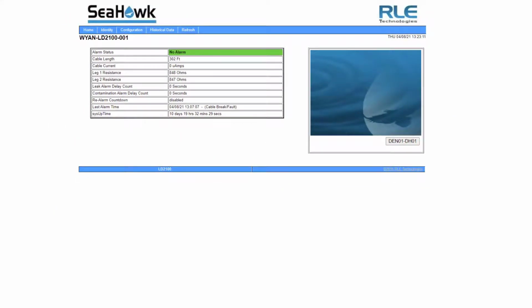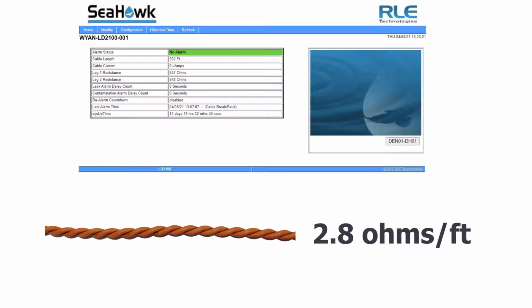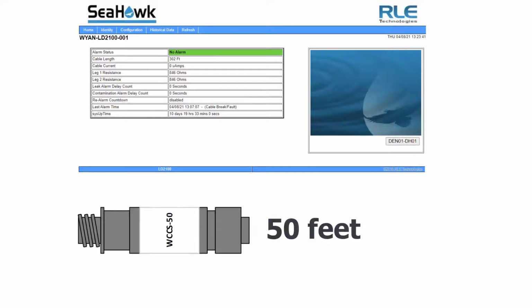So going into calibration, you always want to check for a few optional components being added onto that cable system. The sense cable itself has an approximate 2.8 ohms per foot, but you could have little variations depending on the age of the system. So that's one thing to keep in mind: how much physical orange cable do you have installed onto the system? The next component that simulates a distance is the weighted cable. That weighted cable assembly simulates 50 feet worth of cable. That connector is usually used for jumping across walls into different perimeters, where you want a good designation break from where the leak detection cable stopped before going into the new area to restart its distance marker.